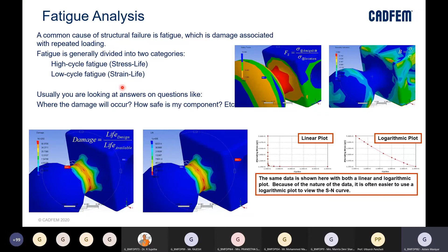For that purpose, I'll show one example here. For this fatigue analysis there is one standard called ISO 7206-4, which is the basic standard for the fatigue test of the hip stem during the gait cycle. You can see on the right side the test setup. You can see where you place your hip stem as the test specimen, then you can apply certain loading for certain cycles, and you can see the fatigue failure after certain cycles.